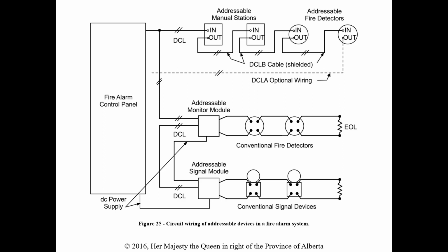The last thing I want to touch on here is under the addressable device fire alarm circuits. They talk about a DCL-B, DCL-A, and DCL-C. So B, again, is similar to class B, but they don't have end-of-line resistors. So even if it's a DCL-B, if it's addressable, we don't have end-of-line resistors. So just make that distinction between a conventional class B and an addressable class B. Now you can see they're still here on these signaling devices. That's because we're using conventional devices, detectors or signals here, with a signal module or a monitor module, so we do need them here. But the devices we saw looping on a class B into an end-of-line resistor, we don't have that in the DCL-B where we actually have addressable devices.